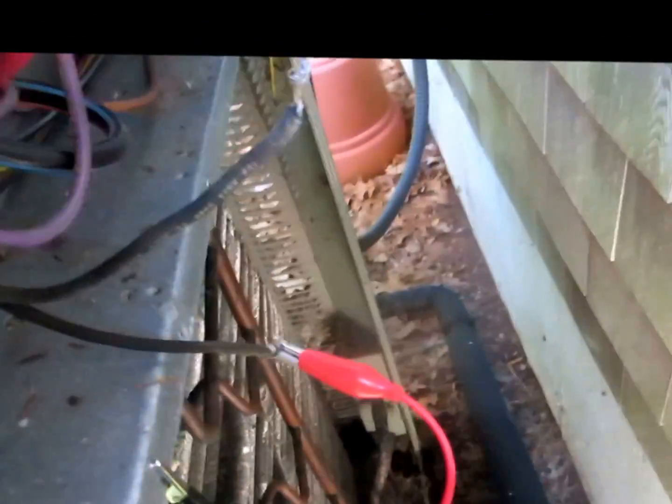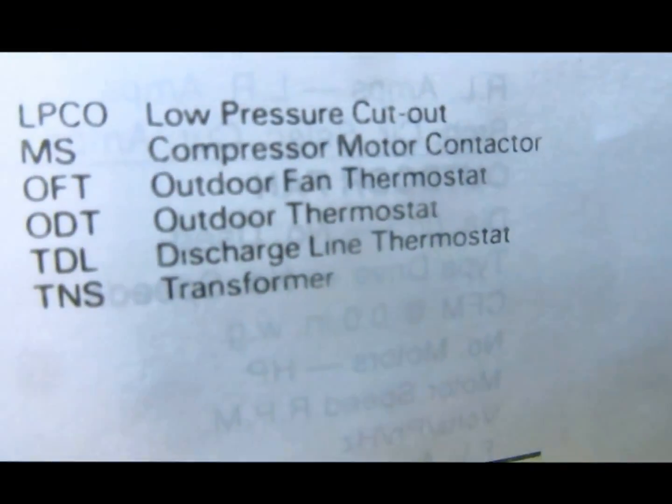Alright guys, I got the two black lines disconnected right here — that's strictly the crankcase heater. So on my wiring diagram right there: crankcase heater, black, black, and TDL discharge line thermostat. This is strictly cooling up here, so I don't even need the crankcase heater. It's only running in the summertime, so I'm just going to disconnect that and fire it up. Let's see if the breaker stays on now. There you go — it'll stay on.